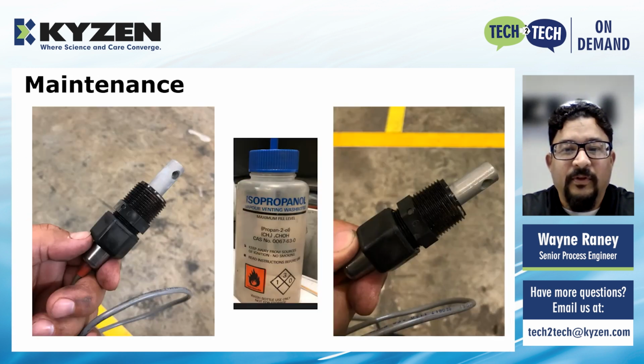This is an example of what a probe looks like before and after cleaning. The probe on the left has a coating on it, and the same probe is pictured on the right after cleaning with IPA. This film can cause a high resistivity, and since the resistivity is the inverse of conductivity, as the resistivity goes up, the conductivity goes down. So this lower conductivity reading can cause your concentration to indicate low, and it'll cause the CCS to add excessive chemistry to try to increase the conductivity to the set point value.